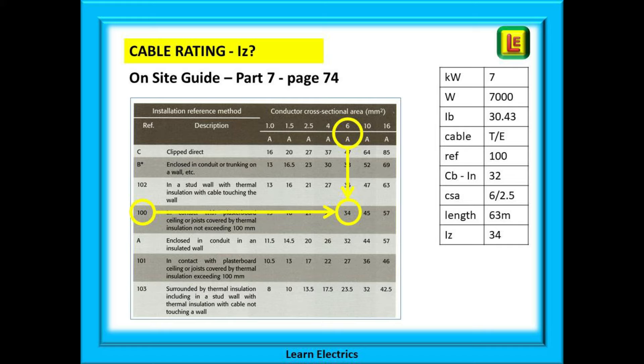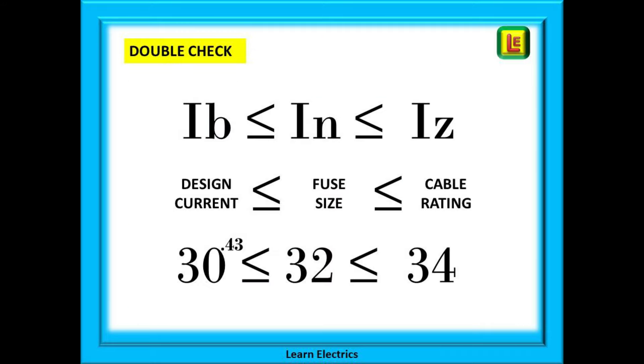Now we have all the information for our shower. A 7 kilowatt shower will draw 30.43 amps. We will use a 32 amp breaker. The cable will take 34 amps and must not exceed 63 metres in length. A quick double check: putting the numbers into IB, IN and IZ — 30.43 is less than 32, and 32 is less than 34. Everything is correct, the job is okay.